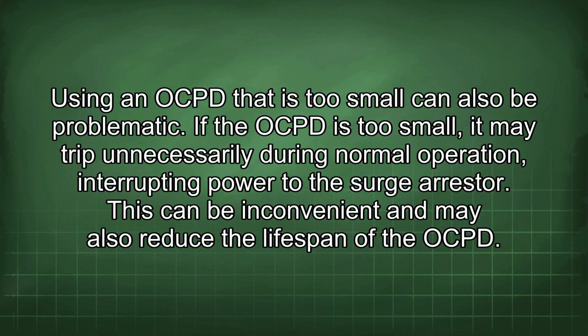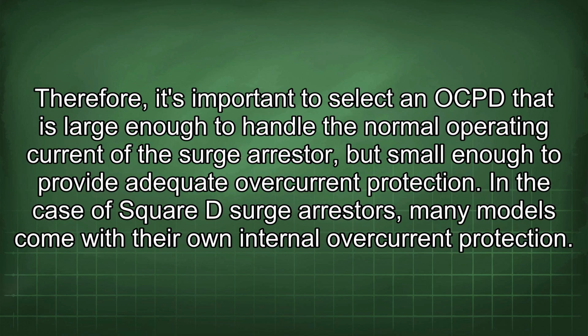Using an OCPD that is too small can also be problematic. If the OCPD is too small, it may trip unnecessarily during normal operation, interrupting power to the surge arrestor. This can be inconvenient and may also reduce the lifespan of the OCPD. Therefore, it's important to select an OCPD that is large enough to handle the normal operating current of the surge arrestor, but small enough to provide adequate overcurrent protection. In the case of Square D surge arrestors, many models come with their own internal overcurrent protection.